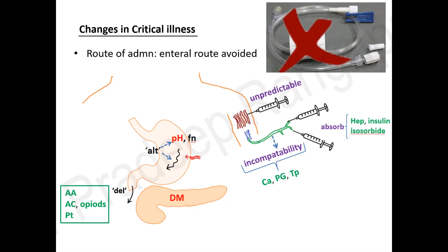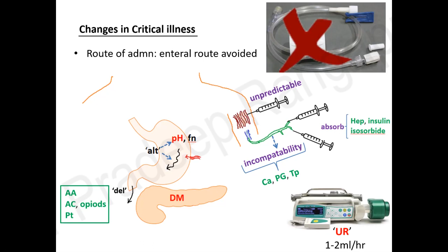And when you are using multiple infusions, sometimes the compatibility of the drug may be an issue, because some of these drugs, like propylene glycol, calcium, thiopentone, can cause precipitation within the tubes and are not meant to be mixed with other drugs. Another important aspect the listener should note is that when we are using infusion pumps at a very low rate, 0.5 ml or less than 1 to 2 ml, the infusion can become erratic. More than 2 ml, they are fairly accurate. Once you keep coming down, like 0.5 or 0.8 ml, the infusions can be quite inaccurate, which one needs to bear in mind.